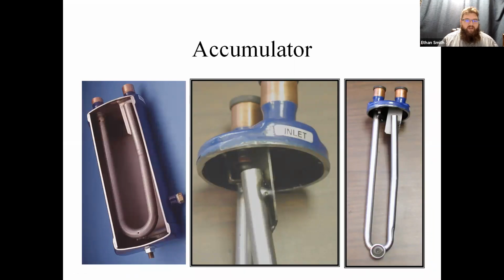So if you are changing out a unit with an accumulator, always, always, always do an accumulator test. That torch test is the easiest way to do it. You do have to do that test once the system is recovered so that you make sure that you don't have a bunch of liquid refrigerant down in the bottom of that accumulator, but it's a good test to do.